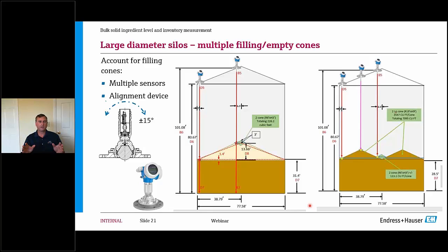Now mass, I'm cautioning about doing that conversion, because the product itself here, depending on how it settles and compresses, you may not always be able to say, okay, this level means this volume and this mass, because the mass might differ depending on how much the product settles in there. But volume you potentially can calculate out quite well.